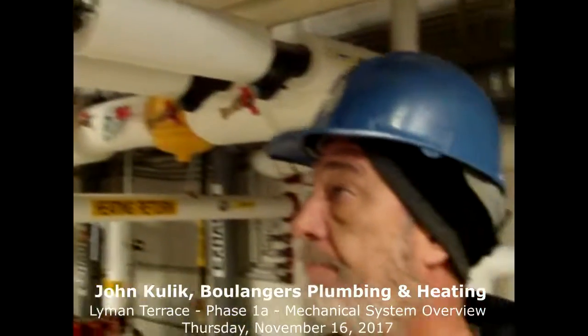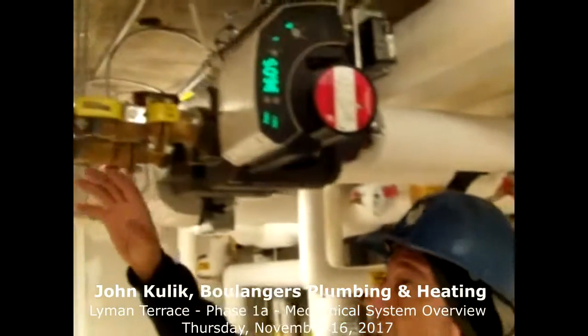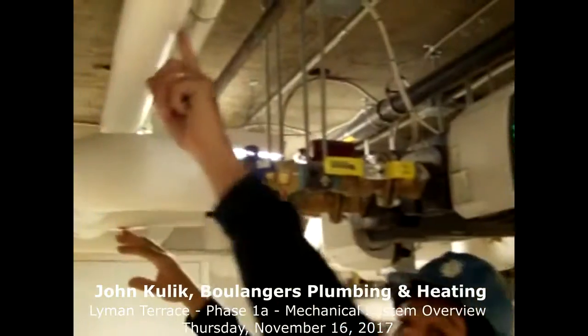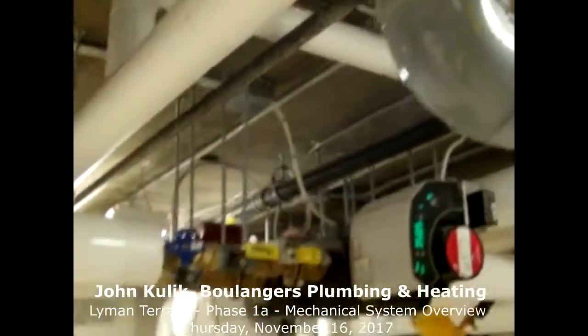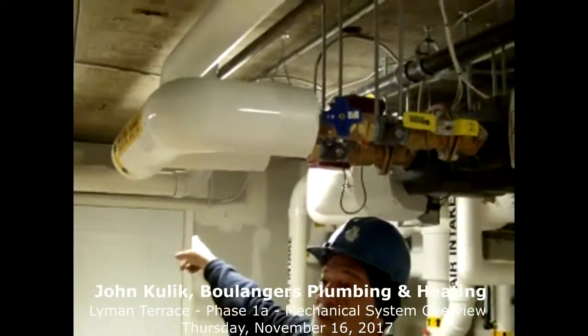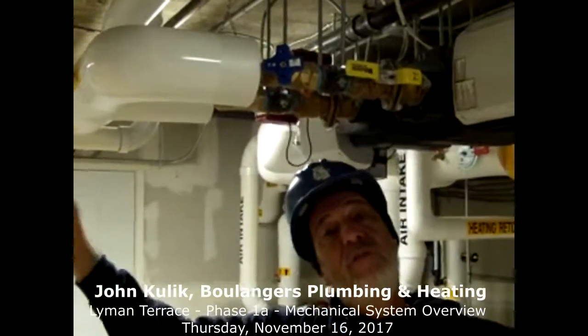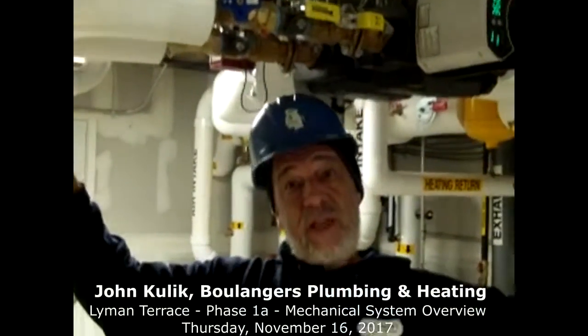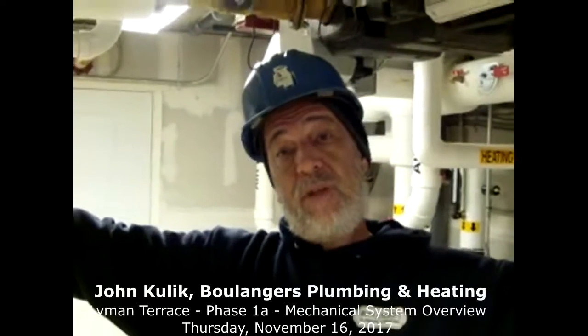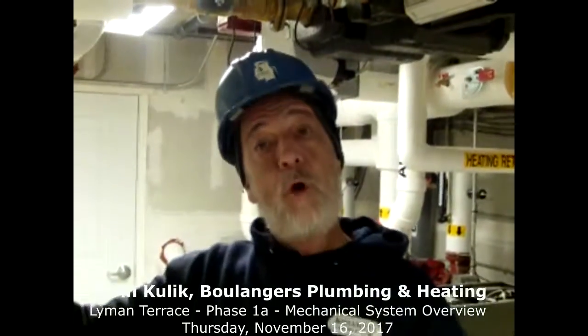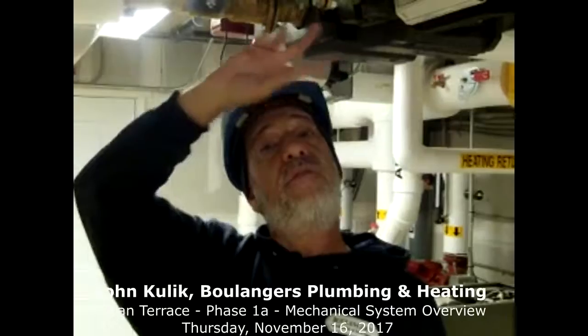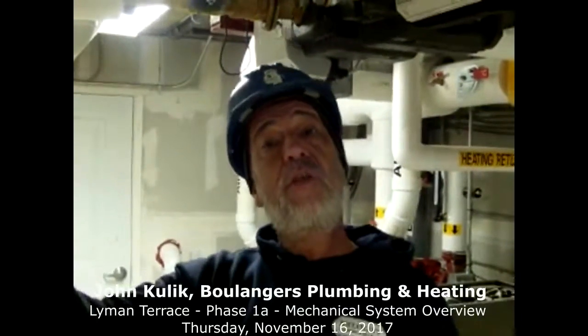Okay. All right, continuing on. The water flows out, goes to one half of the building in this direction, goes to the other half of the building in that direction, up into the apartments through T's that have zone controls on them with the thermostats in the apartments. Thermostat says I'm cool, opens the respective zone valve. The flow will go through that area until the thermostat reaches its desired temperature. At that point, it closes the valve, and the water recirculates just through the main piping, eliminating that.